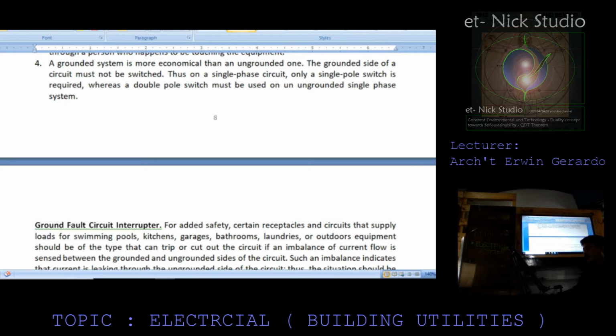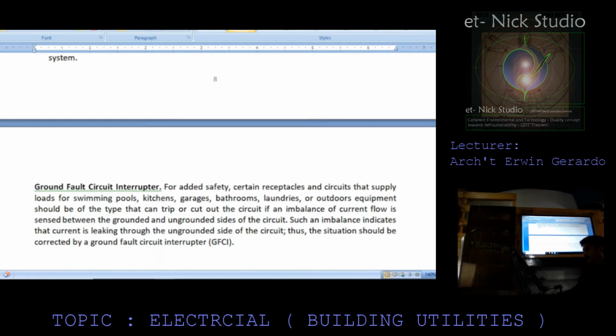Number four, a grounded system is more economical than an ungrounded one. The grounded side of a circuit must not be switched. Thus, on a single-phase circuit, only a single pole switch is required, whereas a double pole switch must be used on an ungrounded single-phase system.